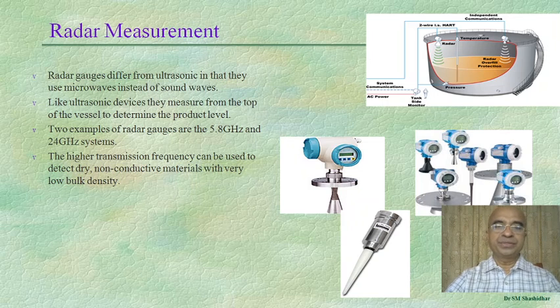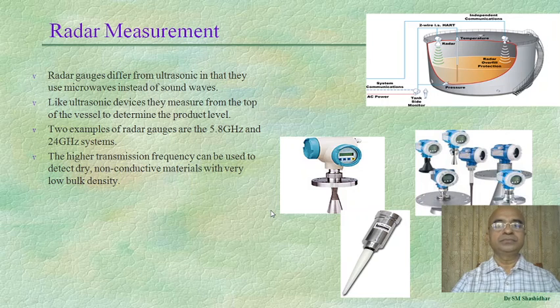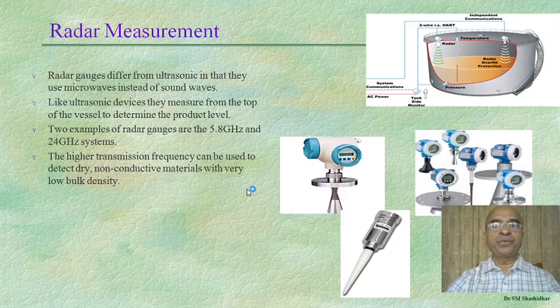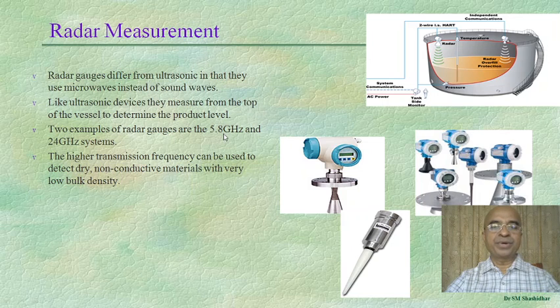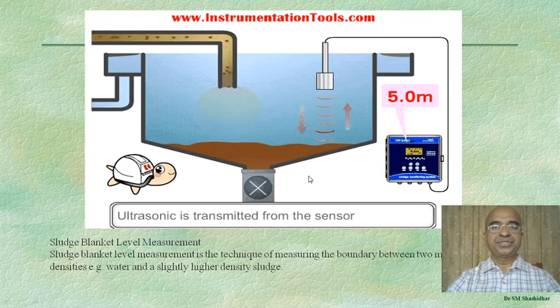Radar measurement uses a similar technique. Radar gauges differ from ultrasonic in that they use microwaves instead of sound waves. The principle is similar to the ultrasonic wave method, but here microwaves of the order of 5.8 GHz or 24 GHz are used.